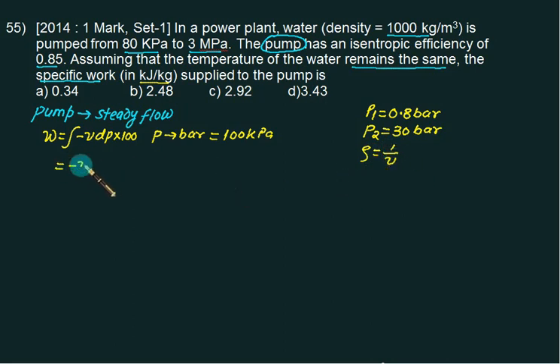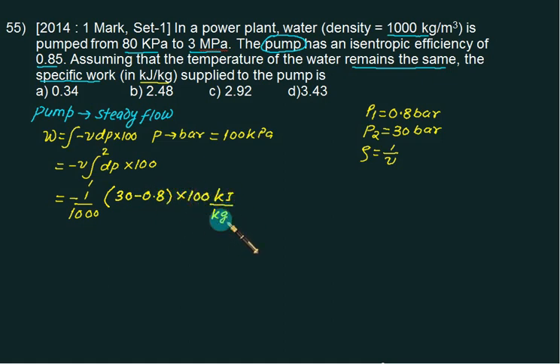We have -v ∫dp × 100 from 1 to 2. So we have -(1/1000) × (30 - 0.8) × 100 as a conversion factor to calculate in kJ/kg. This is our isentropic work, so we have wisentropic = -2.92 kJ/kg.